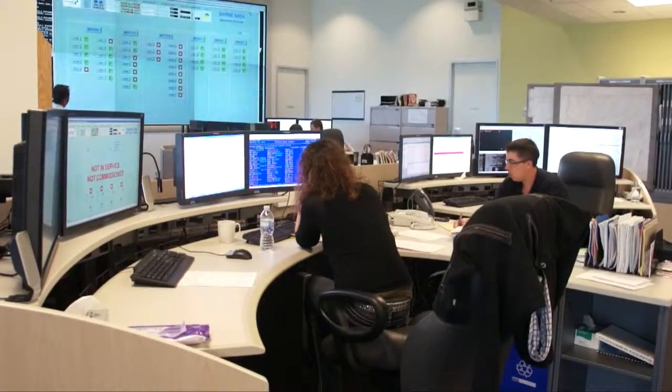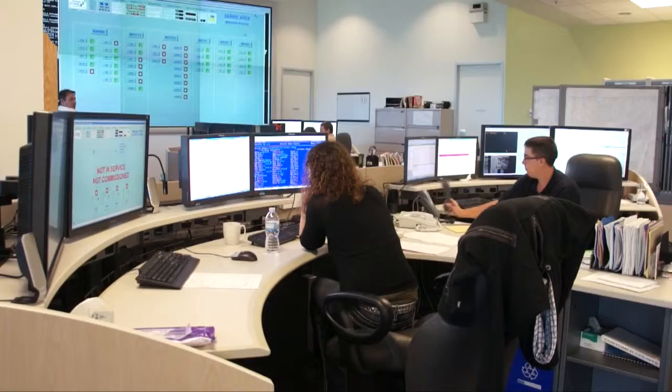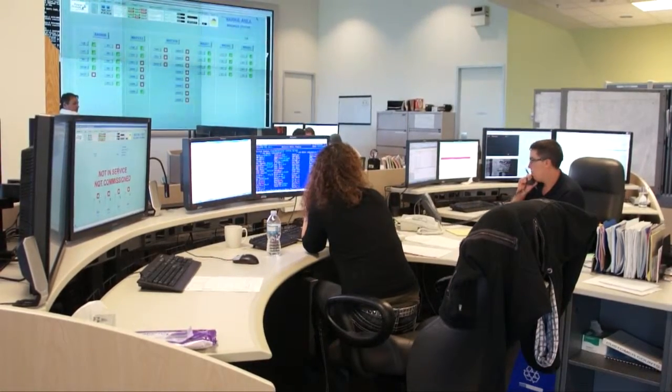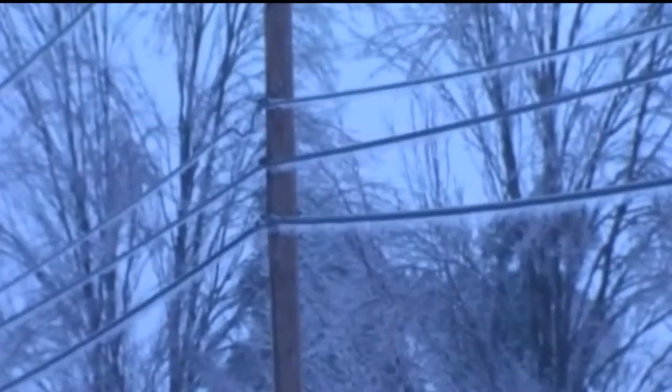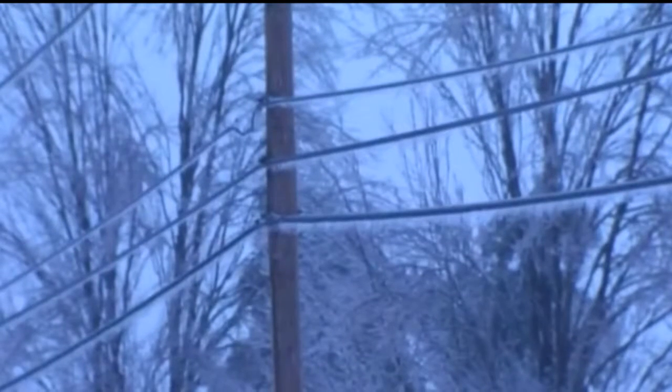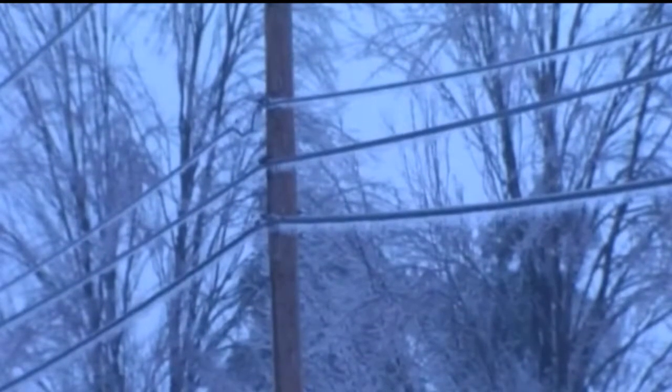And that's where we share the grief, and we'll, on purpose, isolate areas for a certain period of time, typically half an hour to an hour. Then we'll take out another area and restore the original area. And hopefully that will stop any further degradation of the system. But of course, if we lose our transmission supply, then there's not much we can do other than try and reroute power from another transmission source through our distribution network.